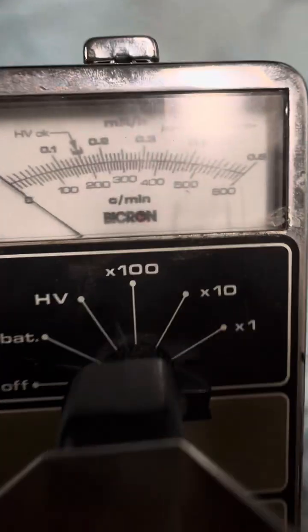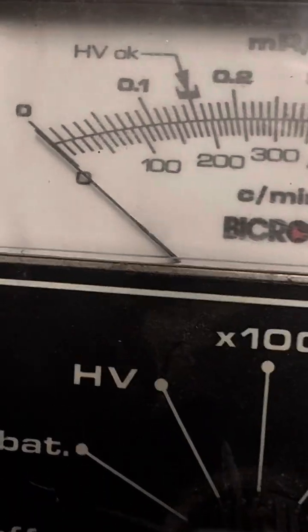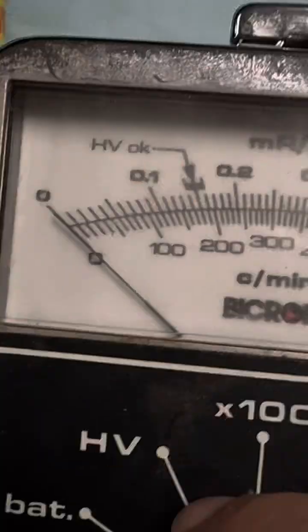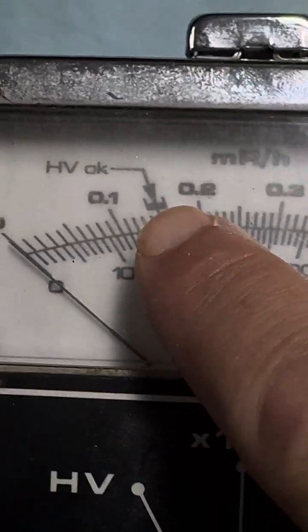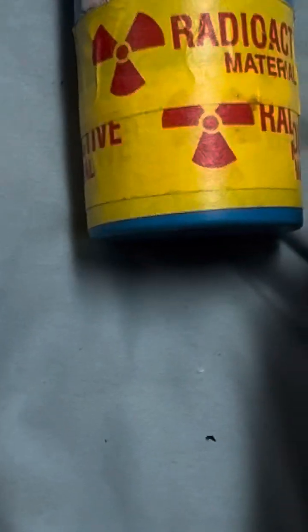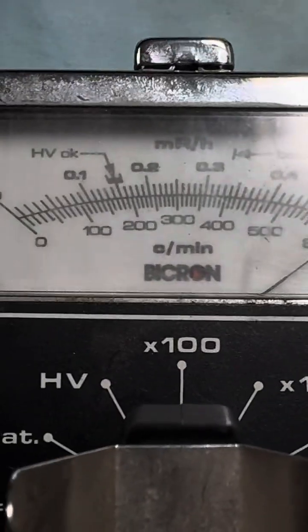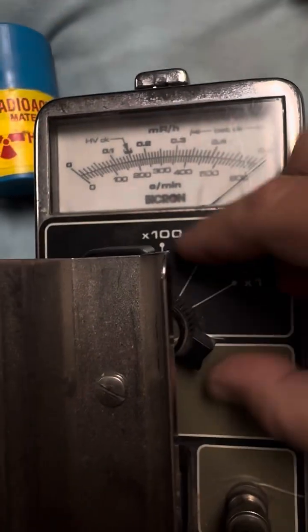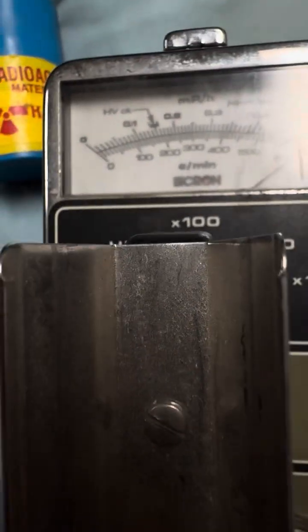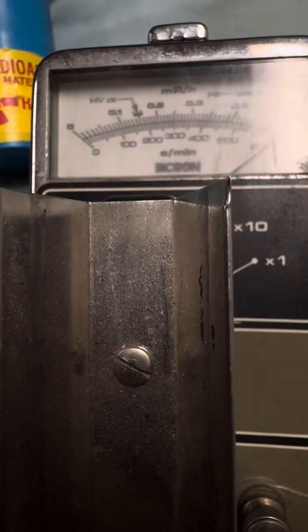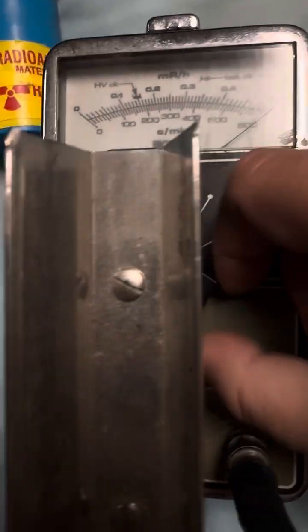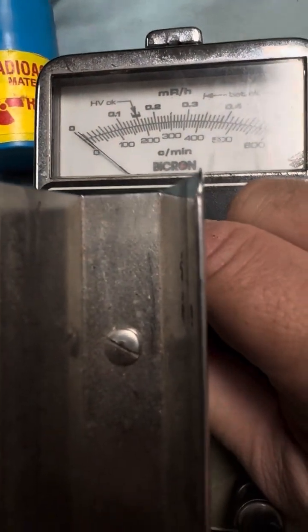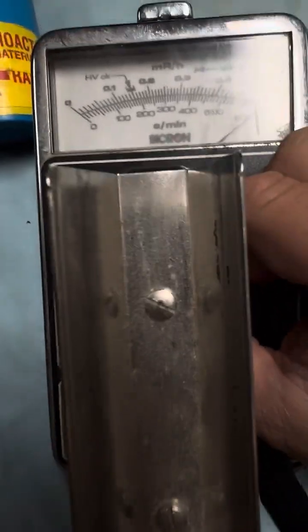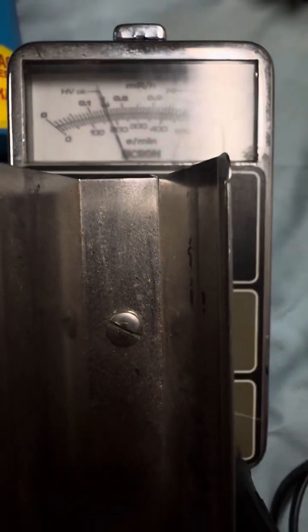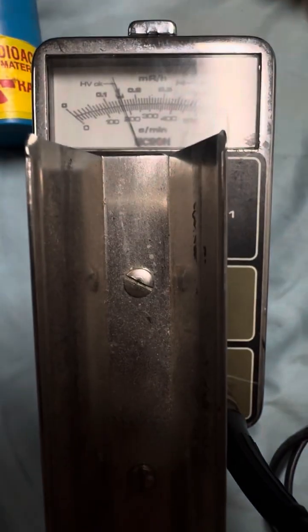So let's zoom in on the scale here. You have an HV indicator right there. It's a very narrow range. So I'm going to show you, that's the battery check. This unit comes with two absolutely brand new batteries. I mean, I just took them out of the case less than 5 minutes ago and installed them. That should give you about 250 to 300 hours of use on the counter. So let's go to HV check. And the HV is okay. That means it's approximately 900 volts.